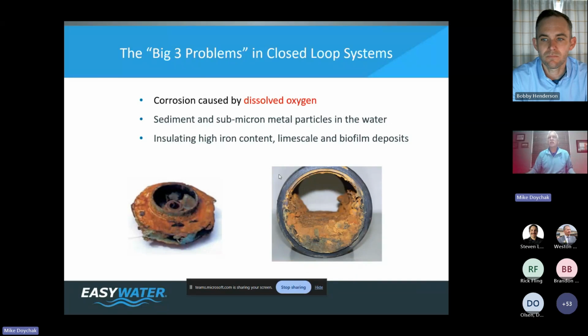When you're talking about closed loop systems, you're really talking about a couple problems that you need to solve. One, the main one, is corrosion caused by dissolved oxygen. That is the problem that leads to everything else. Sediment, very tiny particles, very tiny metal particles in the water, all of those turn into insulating high iron content. Then you get lime scale, you get biofilm deposits. All of that leads to equipment degradation, loss of efficiency, all of that.